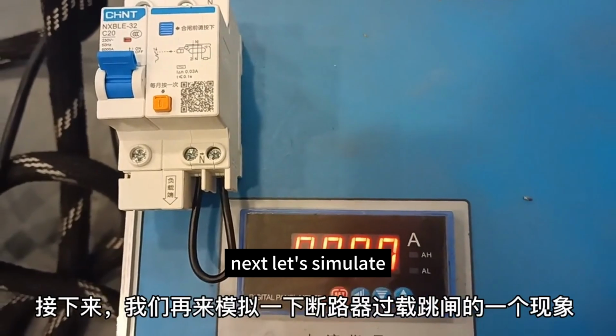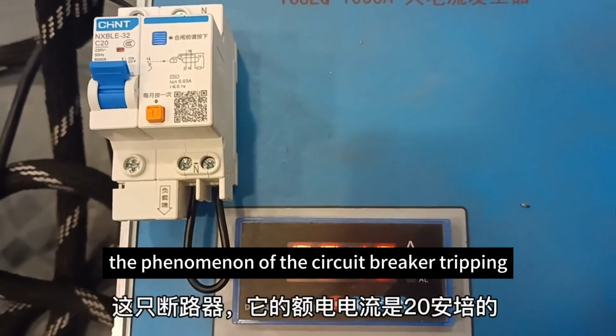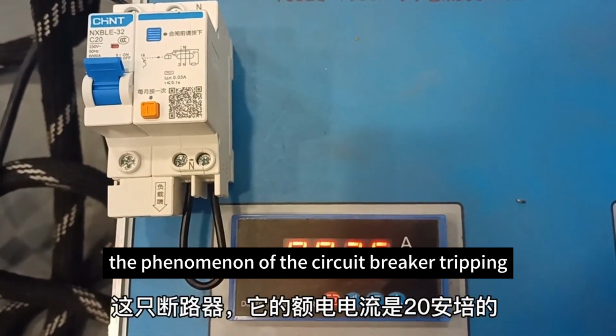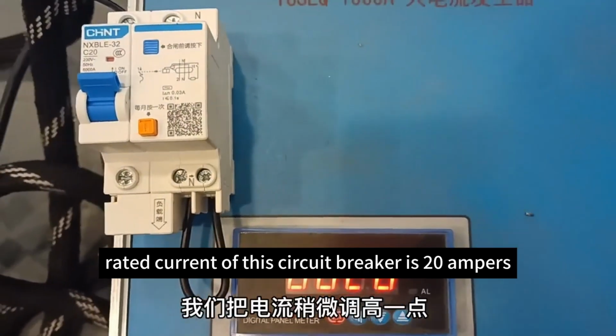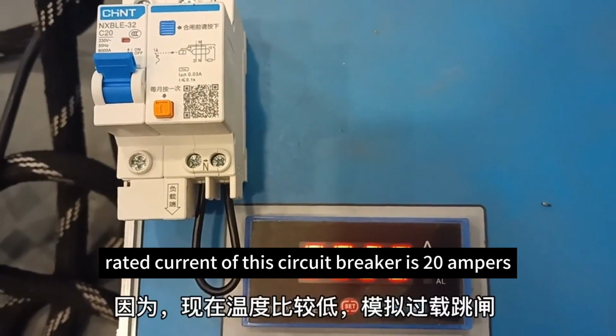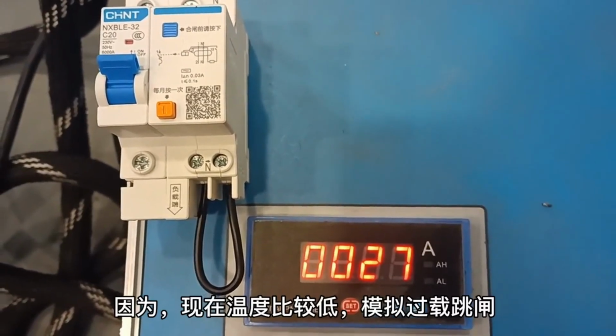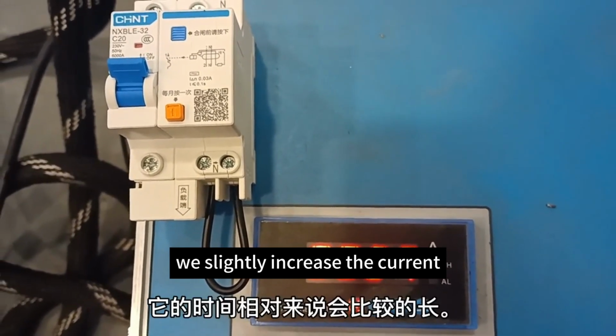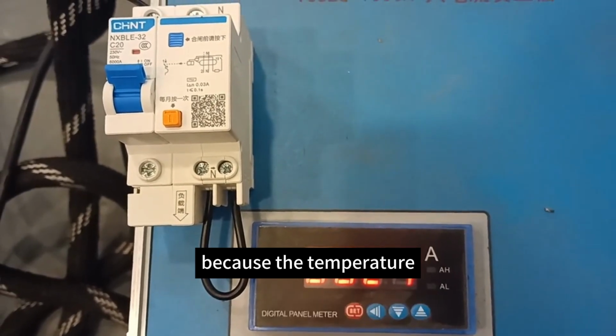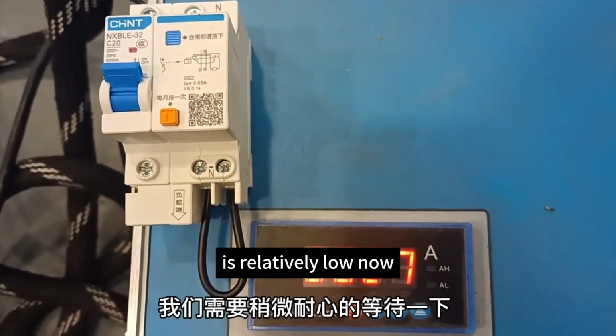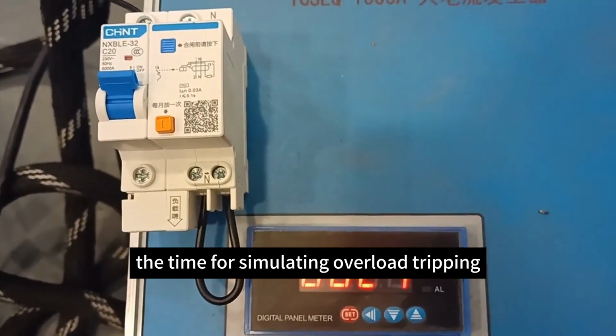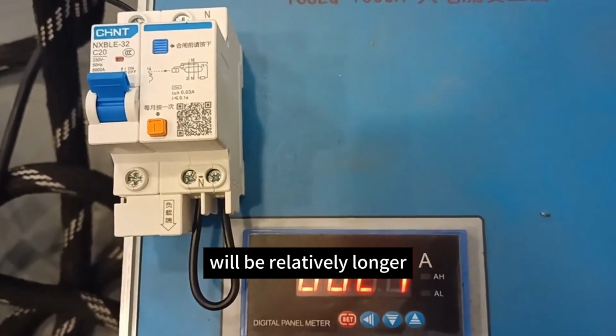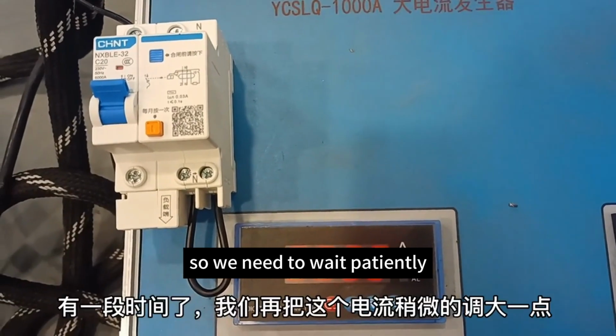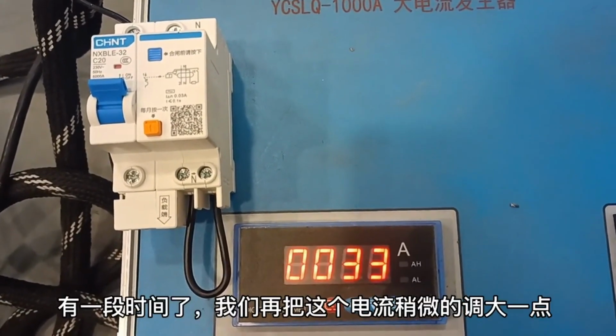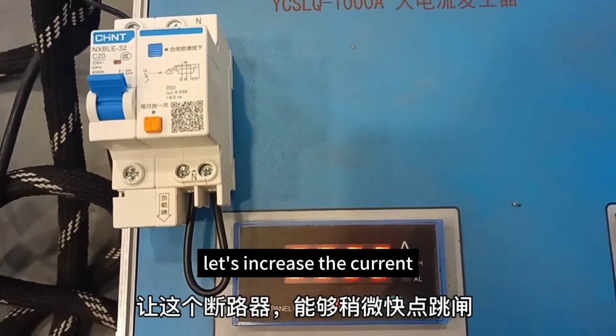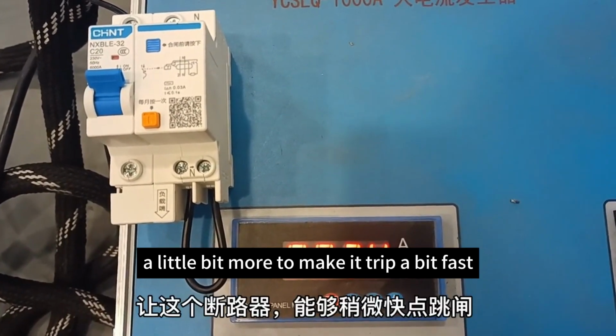Next, let's simulate the phenomenon of the circuit breaker tripping due to overload. The rated current of this circuit breaker is 20 amperes. We slightly increase the current because the temperature is relatively low now. The time for simulating overload tripping will be relatively longer, so we need to wait patiently. It has been a while. Let's increase the current a little bit more to make it trip a bit faster.